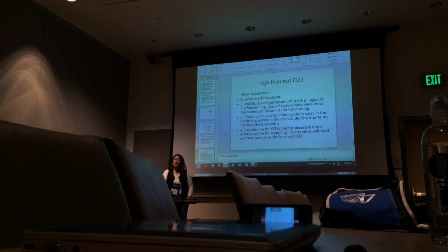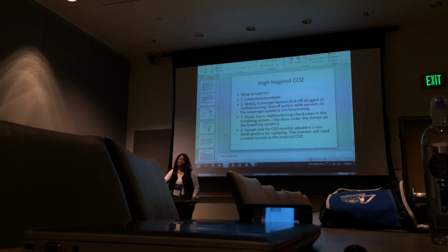Anybody taking a call with high inspired CO2? They're saying that the inspired CO2 on the monitor is not returning to 0. Yeah, high inspired CO2. What you're going to look for, first of all, is exhausted absorbent on the anesthesia machine. They should be changing this out regularly.